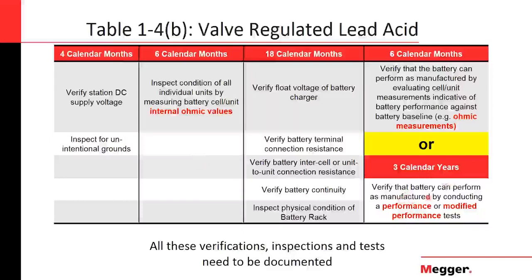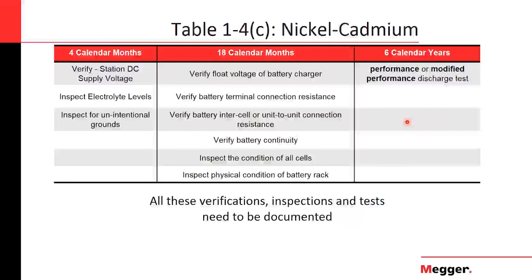The periodicity is higher. Instead of 6 years, it's every 3 calendar years, because again, you can't see through these batteries and they might deteriorate faster. One important thing to highlight here is that if you do the discharge test every 3 years, it doesn't mean that you don't have to do the internal ohmic values. You still need to do the internal ohmic values every 6 months, but whenever you hit the 3 calendar years, that's when you have the option to run the discharge test or keep doing an ohmic test. So in these batteries, you need to do both tests, the ohmic and the discharge test.